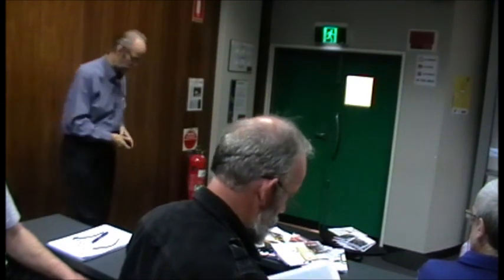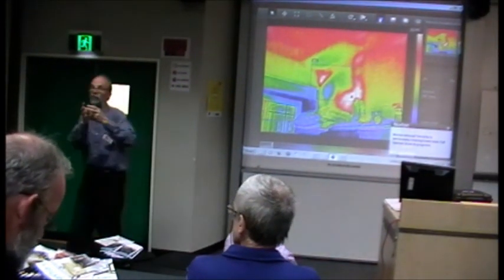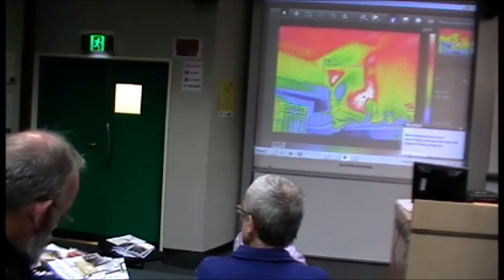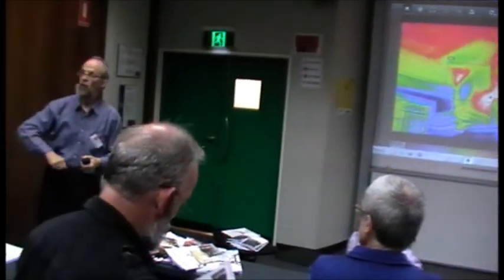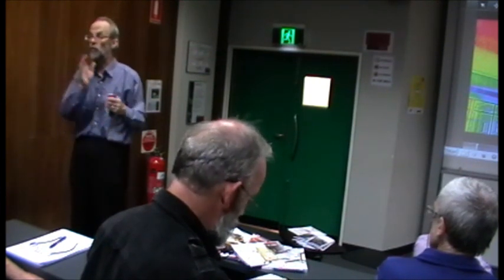If your house has come down, so if we have a cool morning, cool overnight, so it hasn't been a hot day, and the day before, often you have to actually look at the history over a couple of days. You've had your AC and heating off, and the house has now got down to 5 degrees or something. Everything's about the same, and outside is about that. Now we turn the heating on, and you can start looking for those differences. You've got it all nice and uniform to start with, and you'll pick up those differences. And you do it either on the inside or the outside.